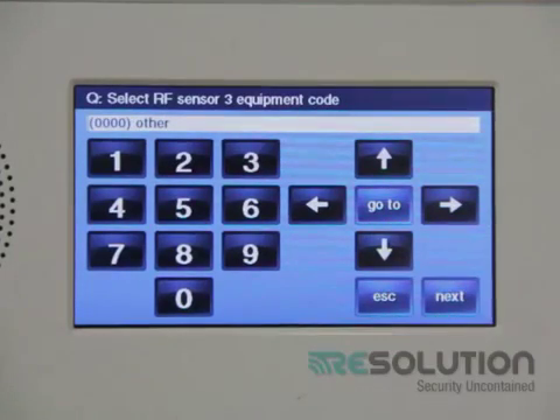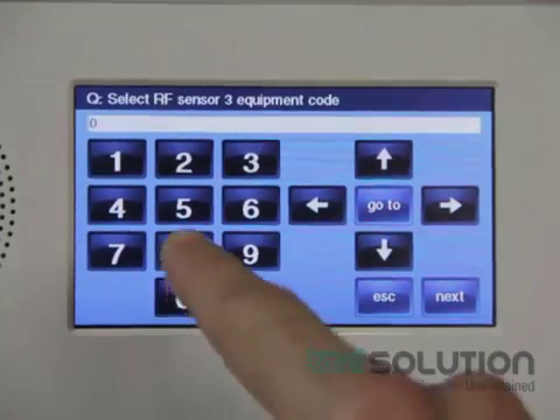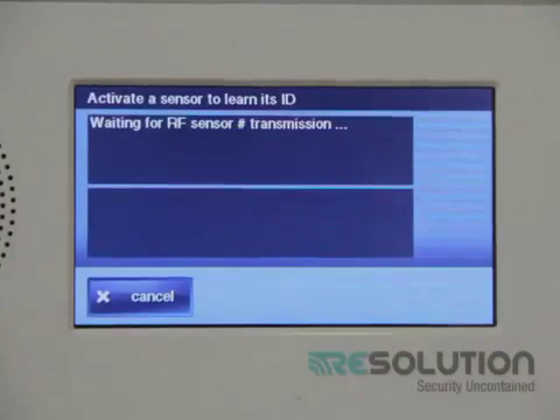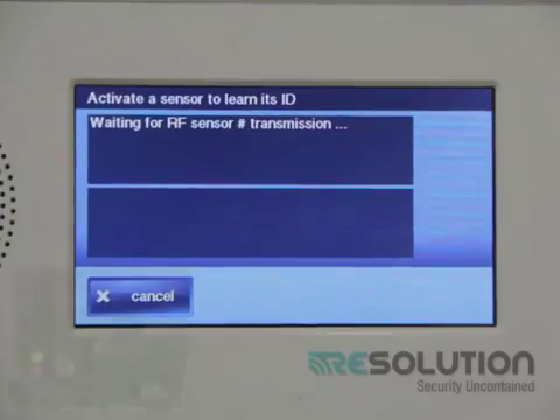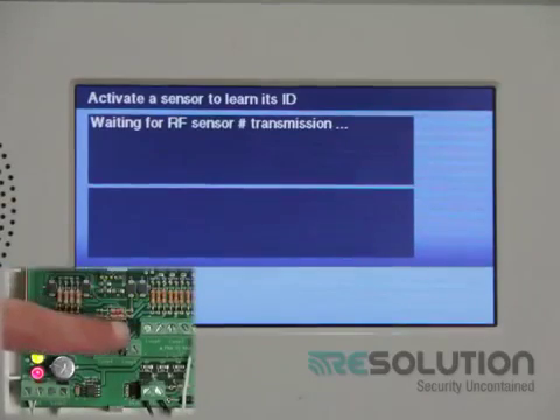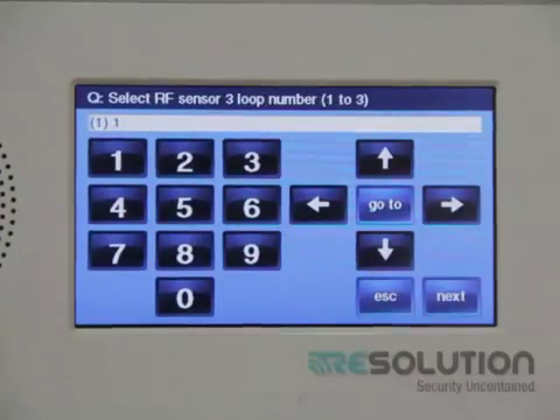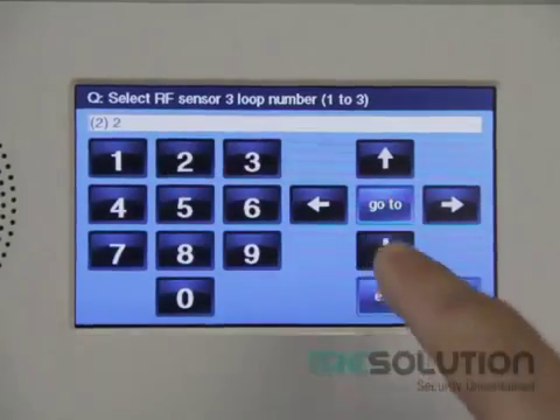I press the down key and enter equipment code 0873. I press the down key, then press the shift key and the learn key. It's now waiting for a sensor to be transmitted, so I go over to my translator and tamper the device itself. I press the next key and select equipment code new. I select loop number 2 and press the down key and save and exit.